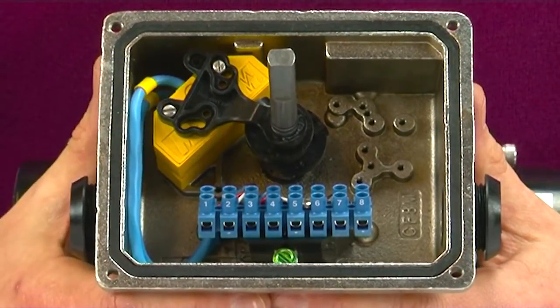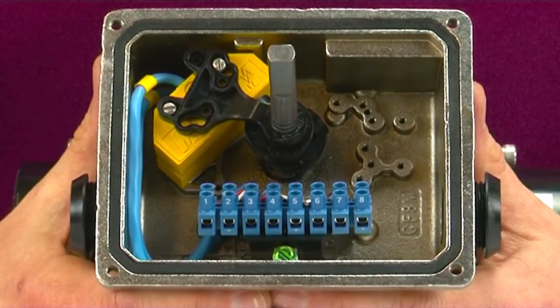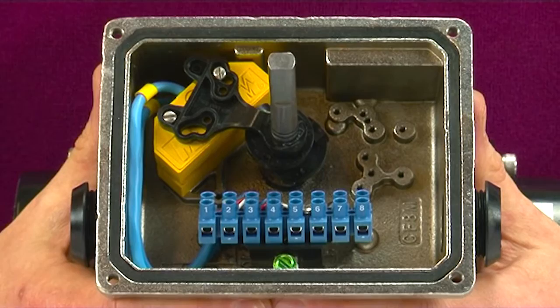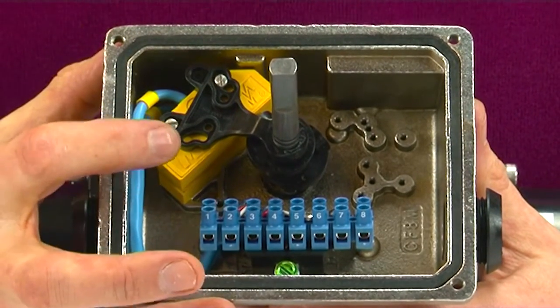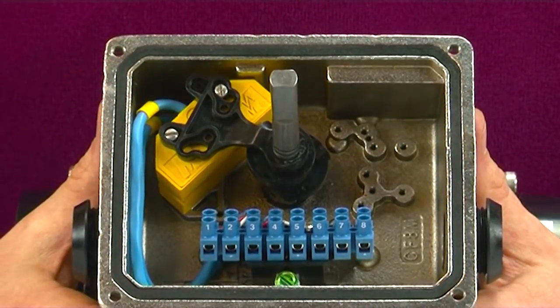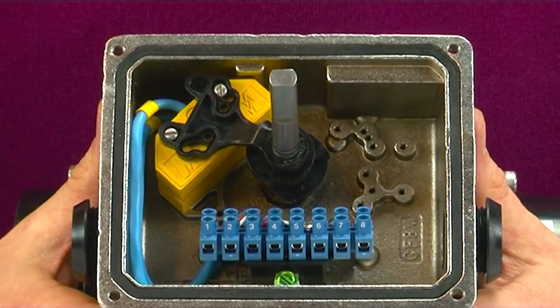The double o-ring seals allow the beacon to be removed without compromising the integrity of the enclosure as previously demonstrated. The shaft and the switch stack are now fitted with a centralisation plate to improve the accuracy and sensing distance between the switches and the cam.